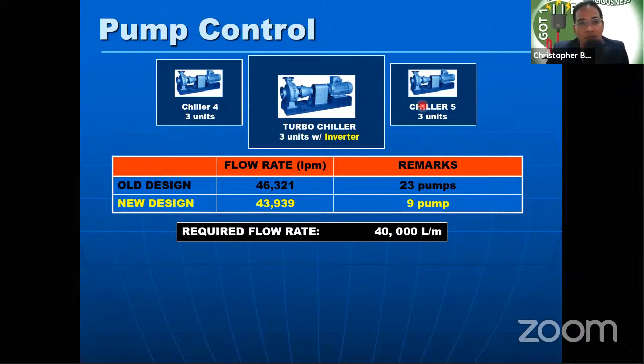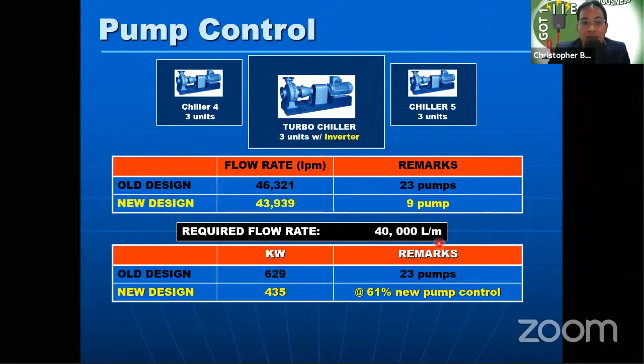So only the ones running variable need them. Going back to our new design, the flow rate needed in our new centralized system is 43,939 liters per minute, and we're now just utilizing 9 pumps. The required flow rate is actually only 40,000 liters per minute. Because we have inverters installed with VFD, we can lower it.